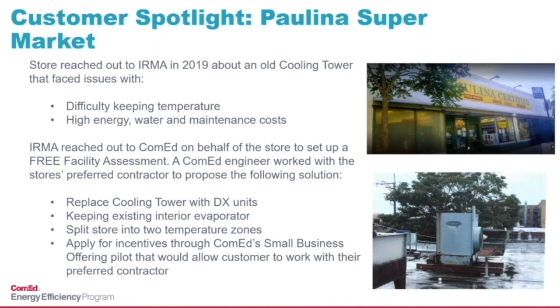We performed the facility assessment and worked very well together to come up with a plan: replacing the old cooling tower with a split direct expansion system, keeping the existing interior evaporator and delivery system in place, and just replacing the heat rejection and compressor system on the rooftop. Basically, we replaced this cooling tower with 4 direct expansion condenser units, about 5 tons each, which also increased the cooling capacity of the system.